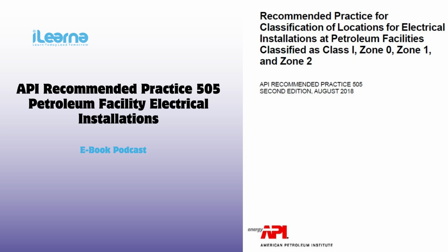Okay. Now, I've heard that there are different classification systems out there. Like there's a zone system and a division system. You're exactly right. It can get a little confusing. Yeah, that's what I was thinking. So how do those two systems fit in with API 505? Well, API 505 specifically focuses on the zone system. And there's another API document, API 500, that uses the division system. They're both aimed at kind of doing the same thing, assessing risk, but they just go about it in slightly different ways. Got it. So we just need to keep those two systems straight in our heads.